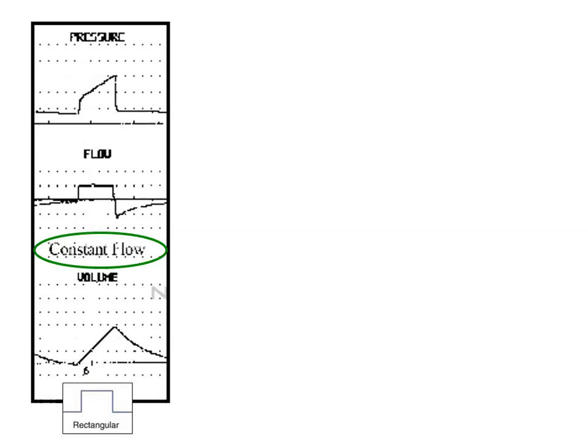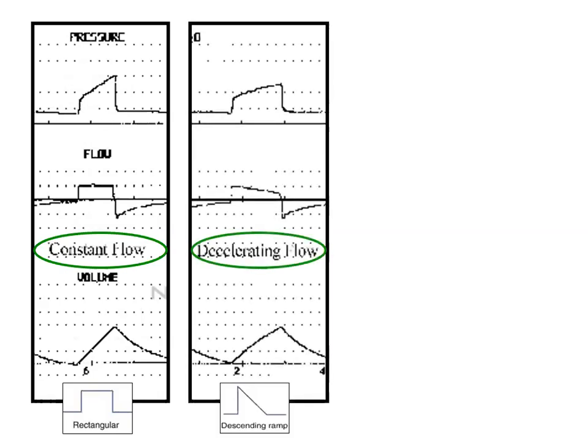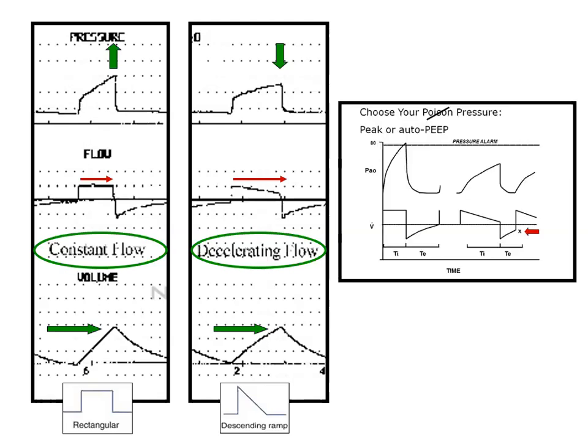So in the square wave, it's a constant flow until the breath is delivered. If you do the decelerating or ramp wave pattern, it on average delivers the same tidal volume over a longer period of time, and by pushing it in over a longer period, the peak pressure goes down. So it's a way of making the beeping stop—going from square wave to ramp wave lowers peak pressures. But you have to choose your poison. We don't like peak pressures because of the beeping and perhaps barotrauma from that. But if you put the breath in over a longer period, as shown here with inspiratory flow on top and expiratory flow on the bottom, you can see there was still flow ongoing when the next breath started.